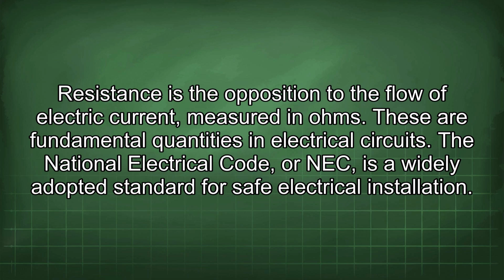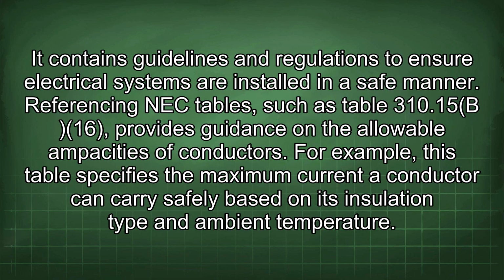The National Electrical Code, or NEC, is a widely adopted standard for safe electrical installation. It contains guidelines and regulations to ensure electrical systems are installed in a safe manner. Referencing NEC tables, such as Table 310.15(B)(16), provides guidance on the allowable ampacities of conductors.